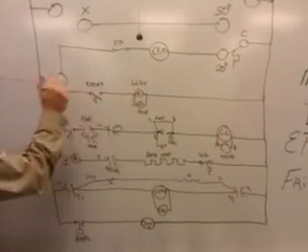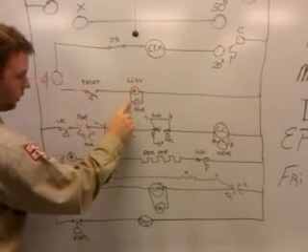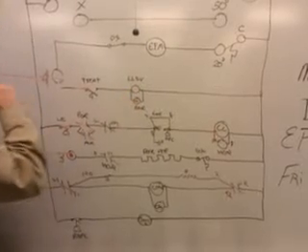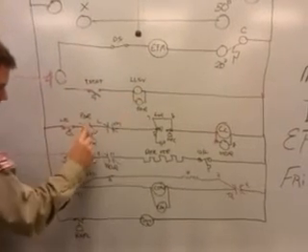Once that happens, it kills power to four, goes over to your LLSV, killing power to your LLSV which closes your cylinder valve, sending the system into a pump down. It also kills power to your POR, which opens up your POR.